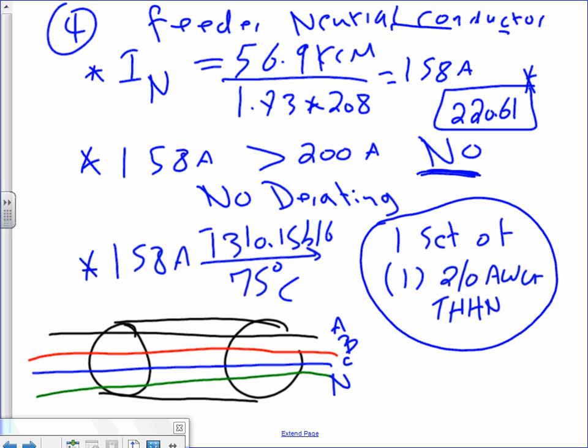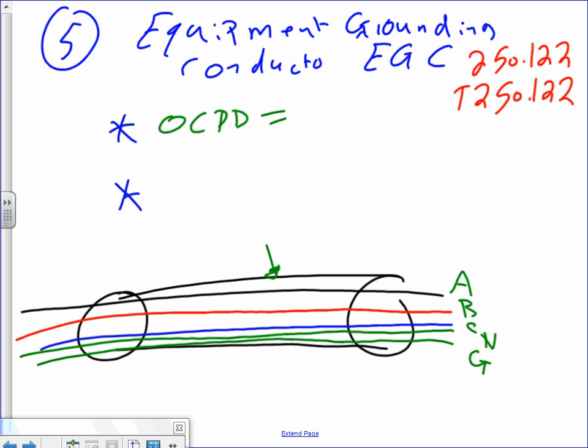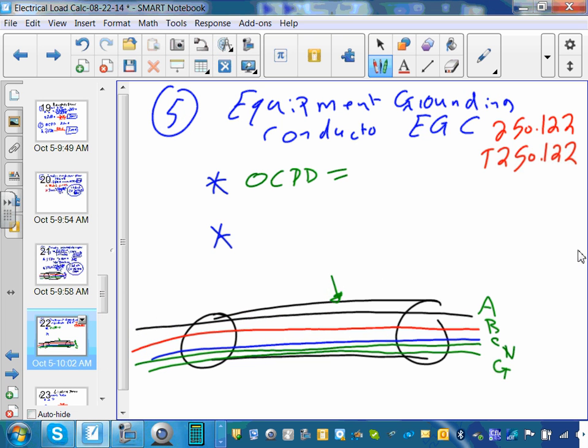We might be able to smuggle another panel, guys, before they come. Let's go equipment ground conductor. For equipment ground conductor, number 5, equipment ground conductor, go to 250. Let's go to this one. 250.122, guys. Table 250.122, please.